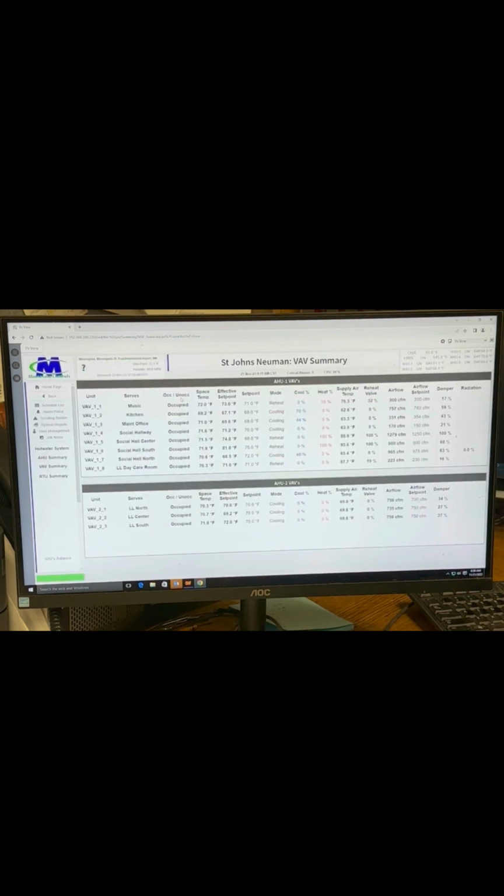Okay. Very important to go through and set your unoccupied heat and cool set points, because they're all out of whack. And if I were you guys, I would set a standard, let's say 66 and 75, and then you can modify it if need be. You know what I mean? And typically, where do you put your temperature set point? What's reasonable? Is it 69, is it 70?